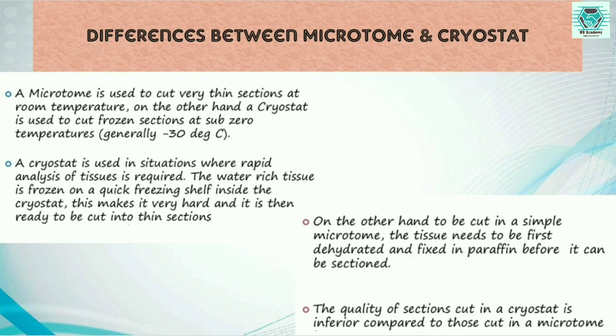What is the difference between a microtome and a cryostat? A microtome is used to cut very thin sections at room temperature, whereas a cryostat is used to cut frozen sections at sub-zero temperature. A cryostat is used in situations where rapid analysis of tissues is required. The water-rich tissue is frozen on a quick freezing shelf inside the cryostat, making it very hard and ready to be cut. In a simple microtome, the tissue needs to be first dehydrated and then fixed in paraffin before it can be sectioned. The quality of sections cut in a cryostat is inferior compared to those cut in a microtome.